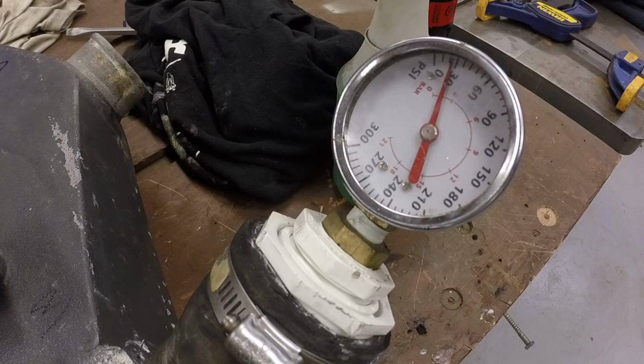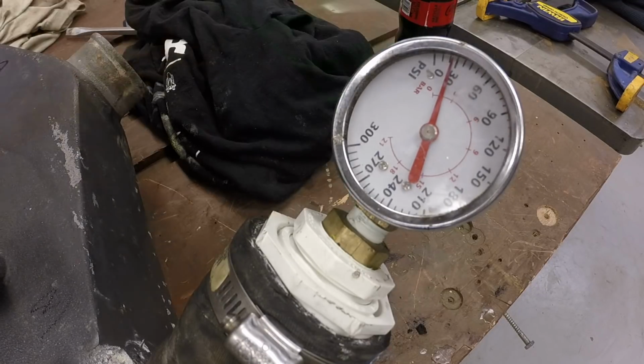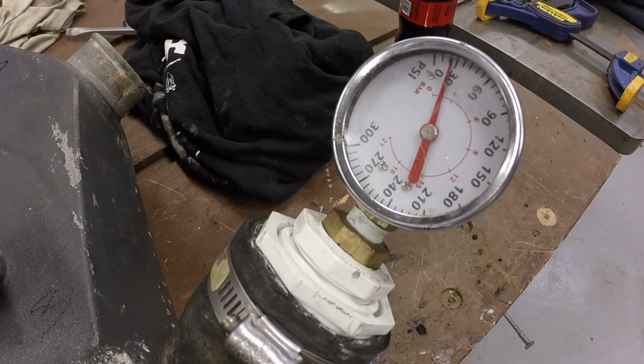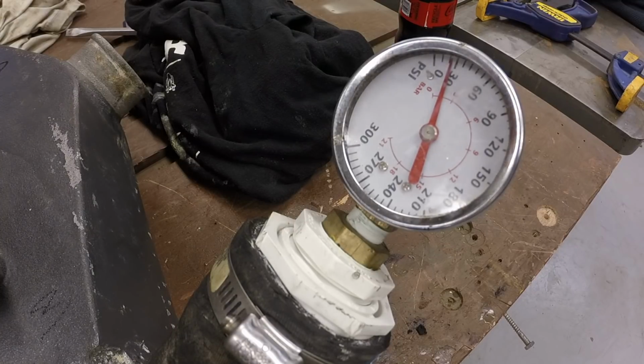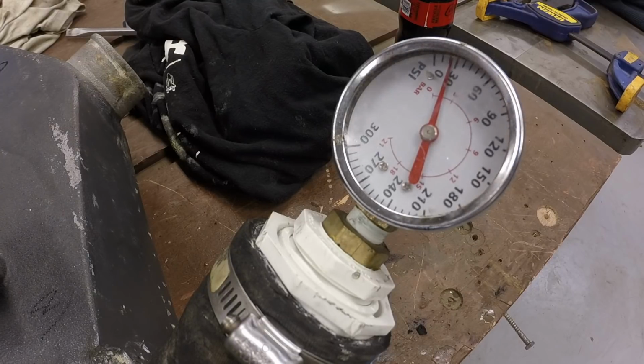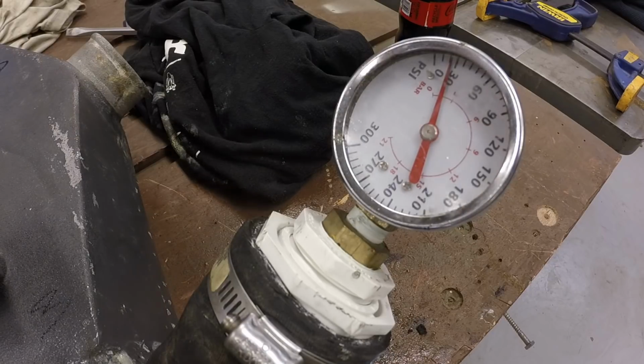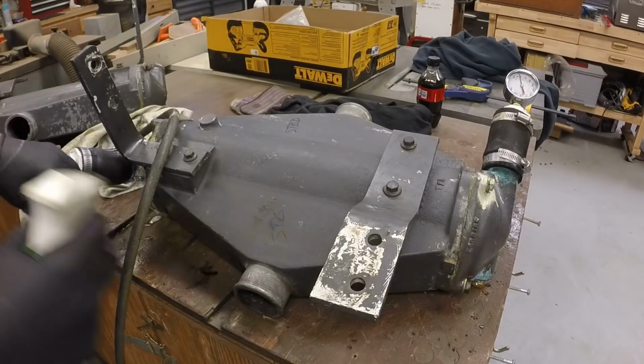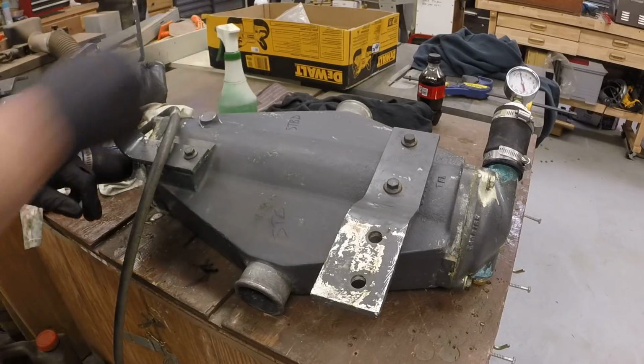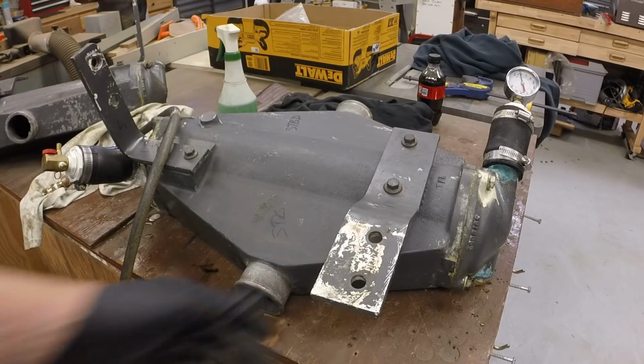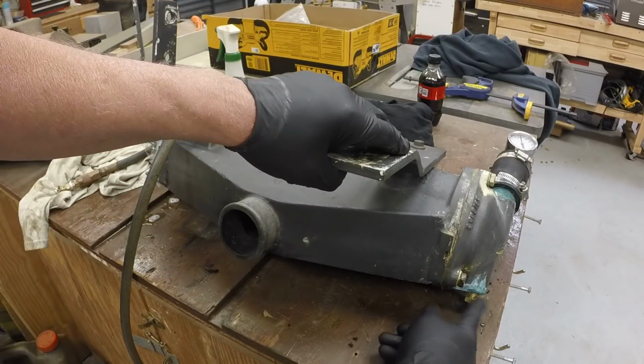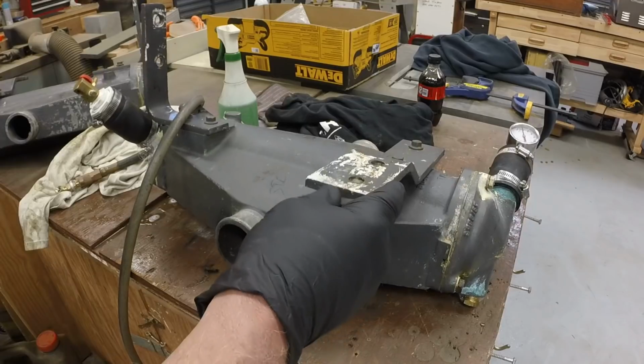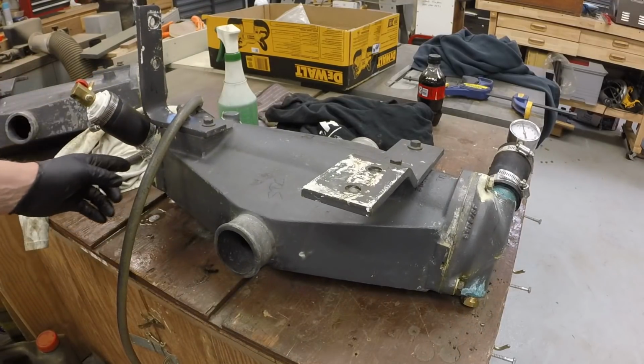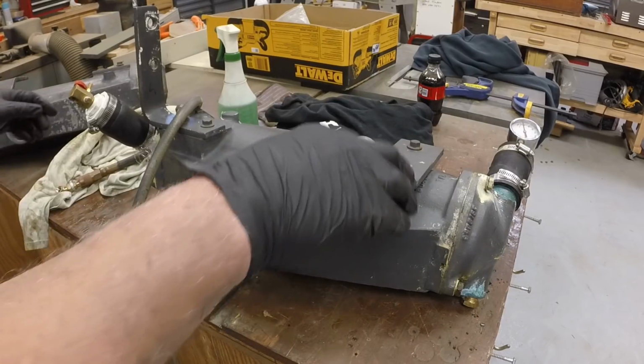Alright, that's over 20 pounds. Let that sit for a second here, check for leaks. All right, I don't see the gauge moving at all. I sprayed soapy water on the hose connections here where I had some minor leaks on the other cooler. Oh, okay, so look, I got bubbles - I got bubbles in two places, this zinc and then over here on this other hose. All right, let me see if I can tighten the hose a little bit more.